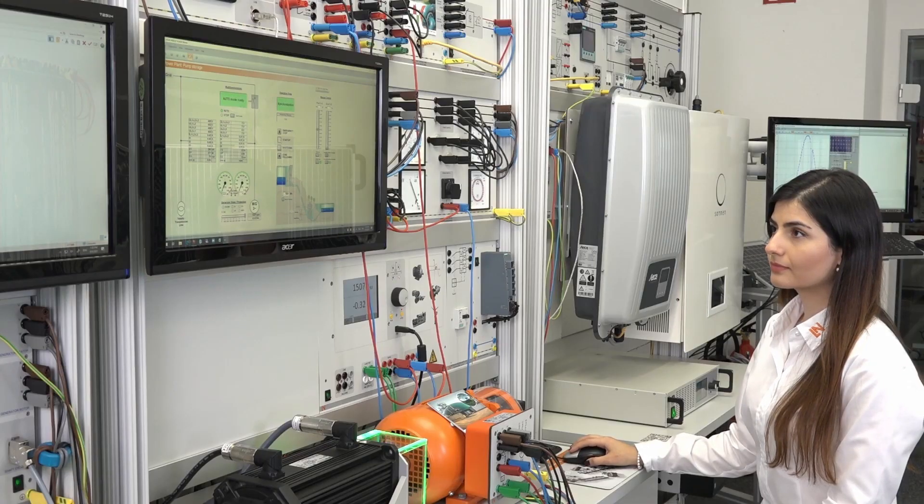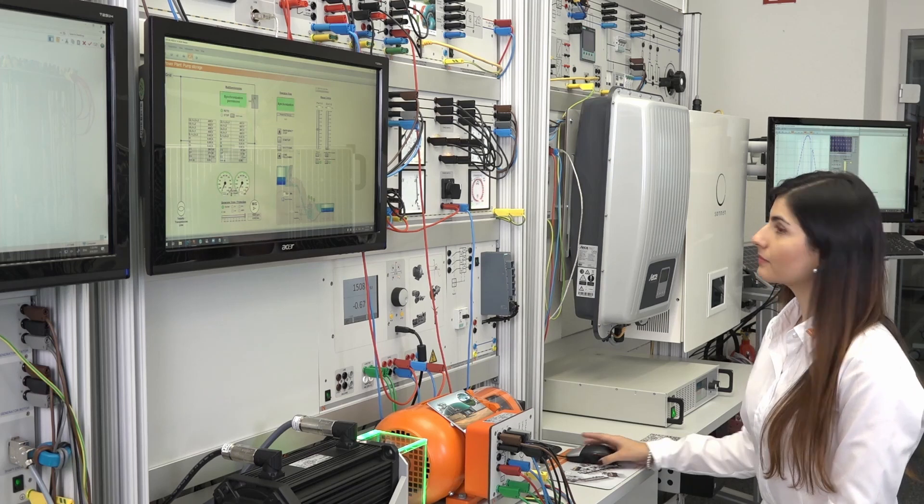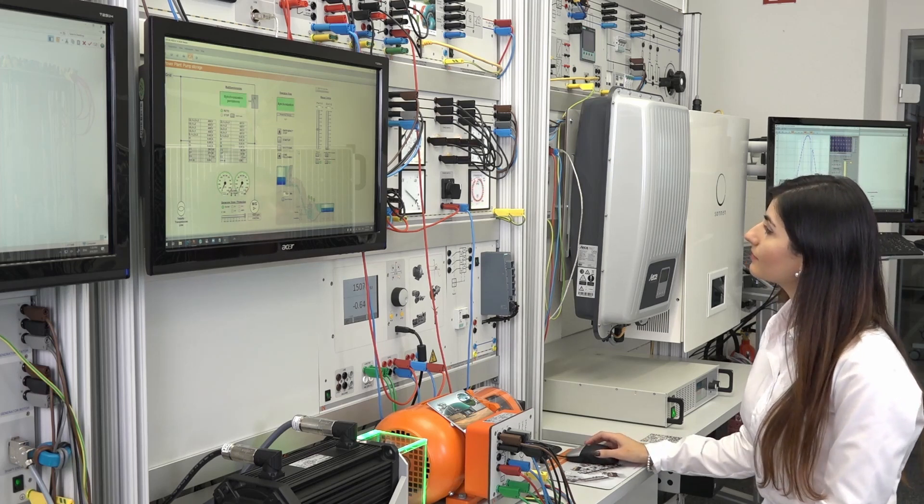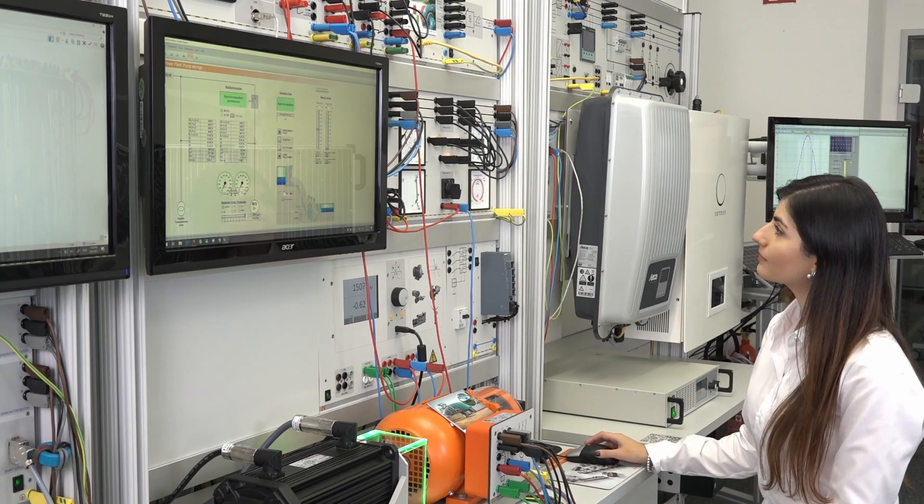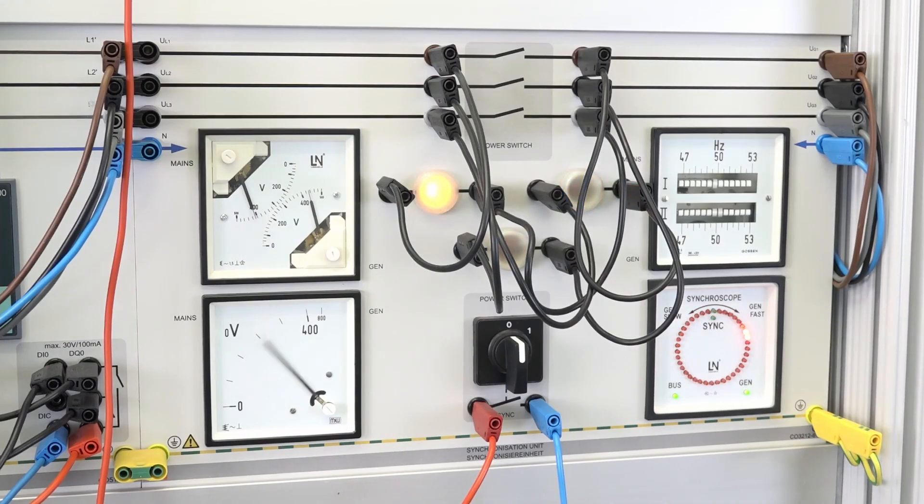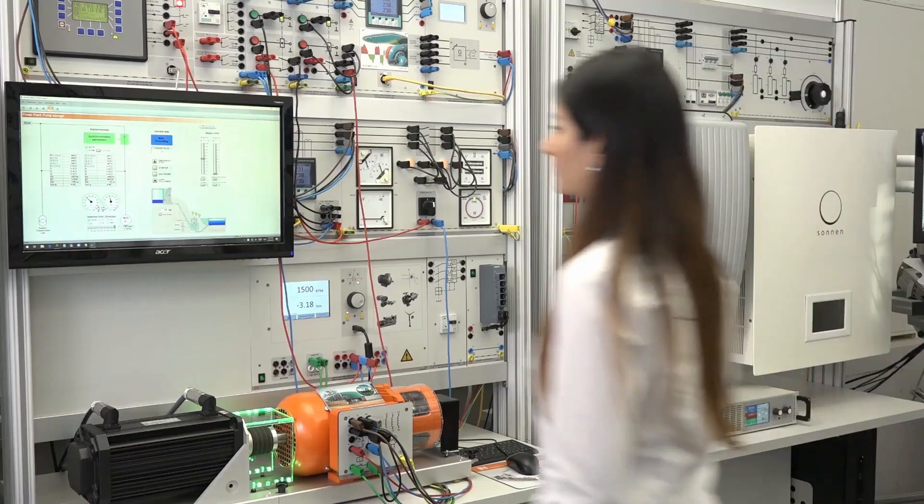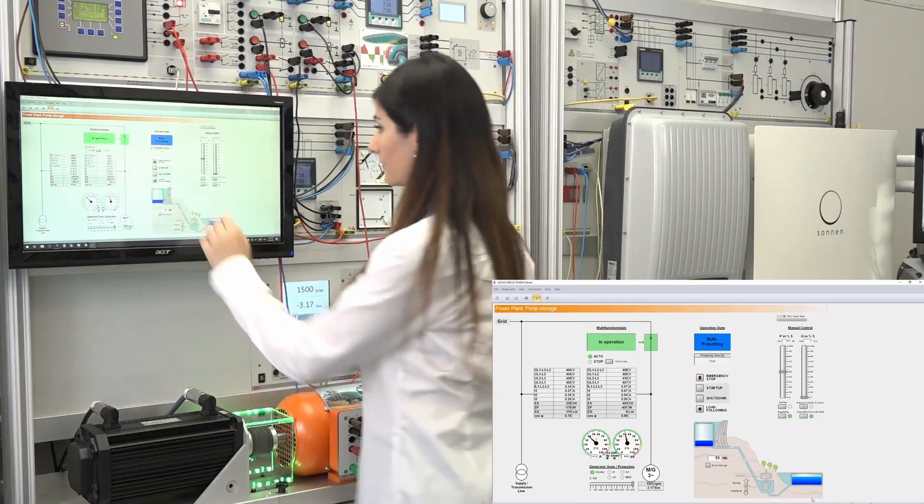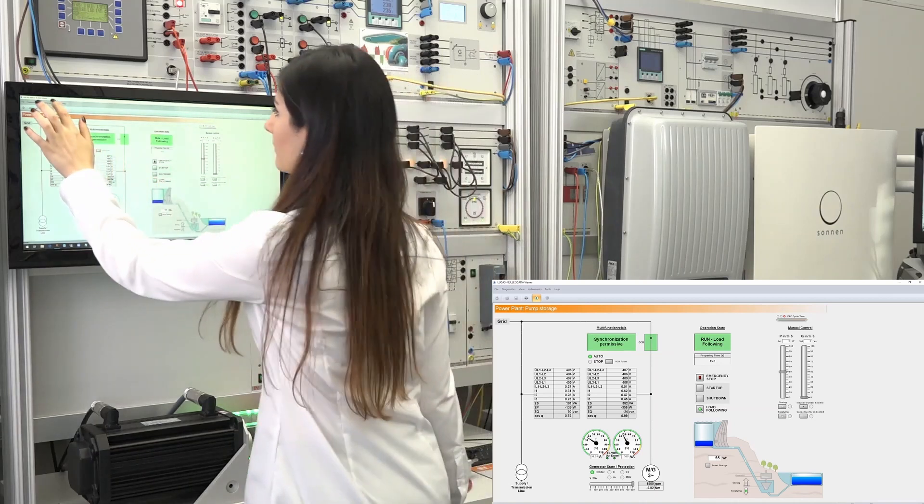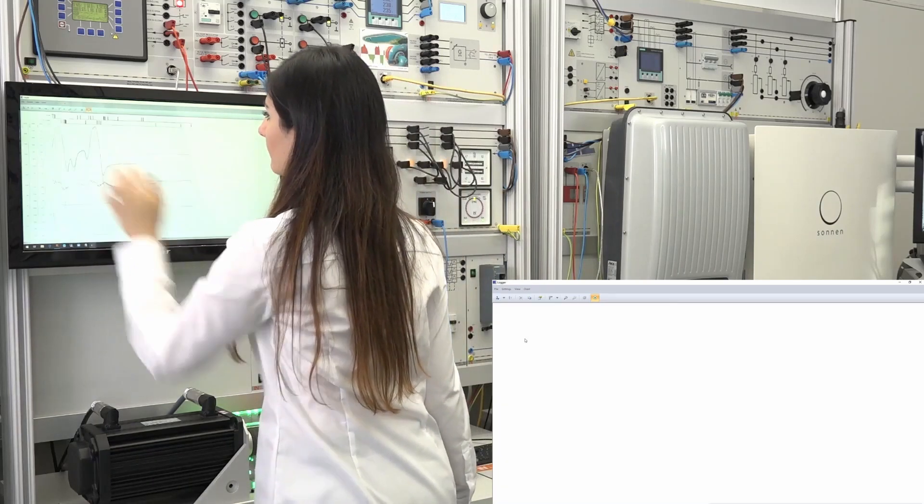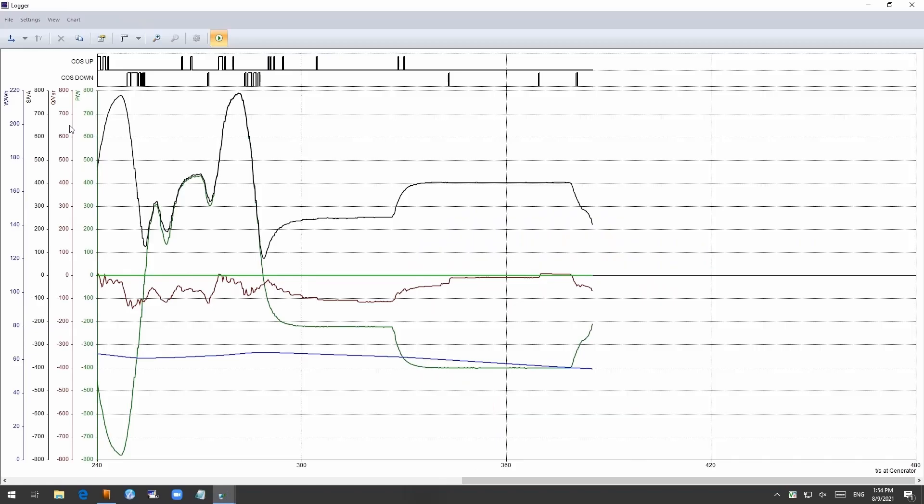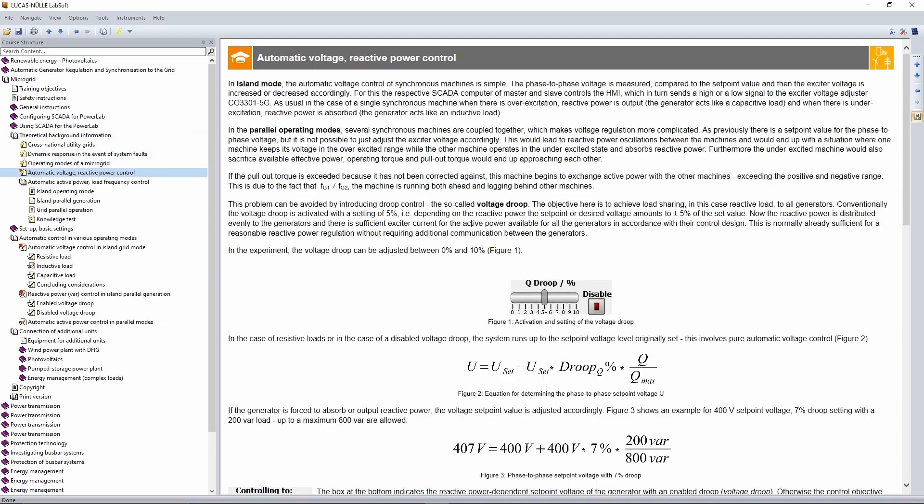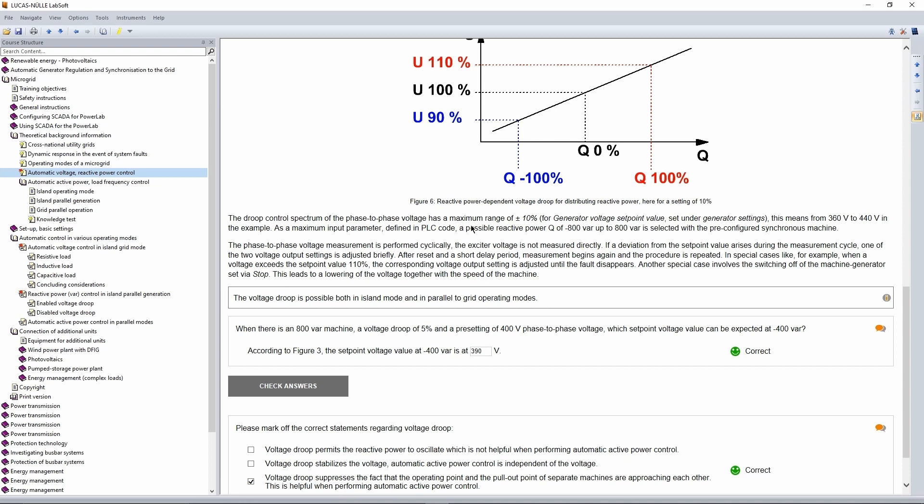An island operation of one or more generation units forming a microgrid is as well feasible. Here, the main generator sets the parameters to form a grid in an island operation and then the effects on frequency and voltage can be observed when connecting loads or other generators. Different controlling techniques such as droop control are used here to stabilize the system and reduce fluctuations.